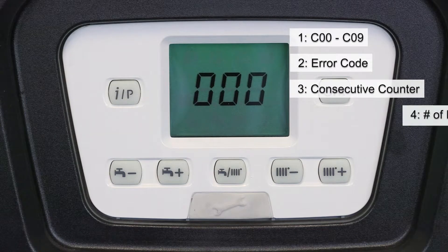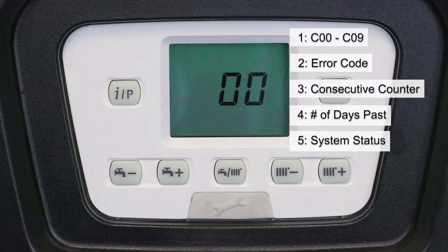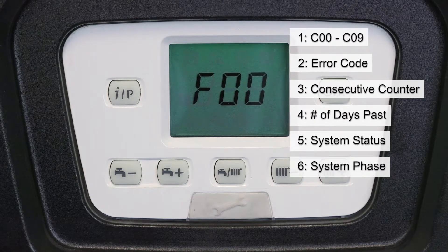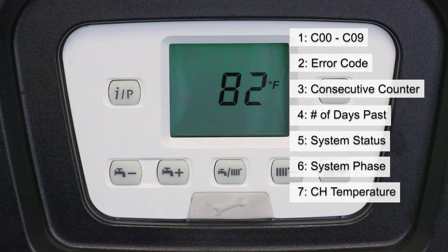The fourth number tells you how many days have passed since the error. The next number is the system status, followed by the system phase, and finally the temperature of the boiler at the time that the error code occurred.